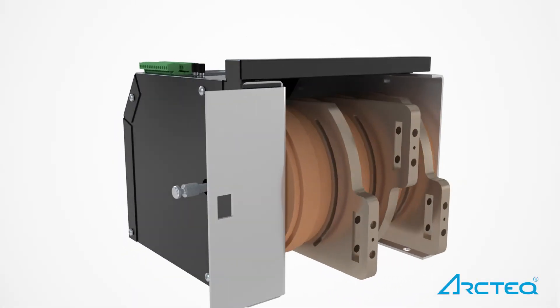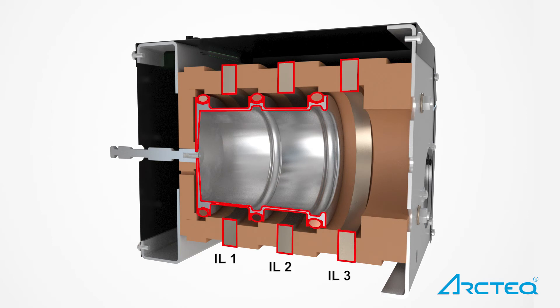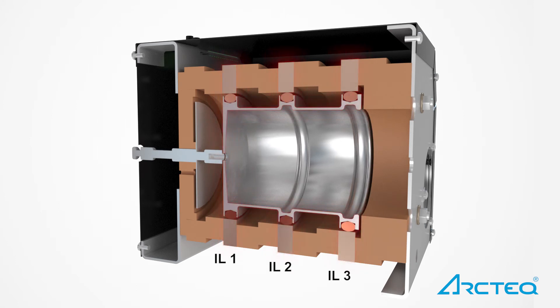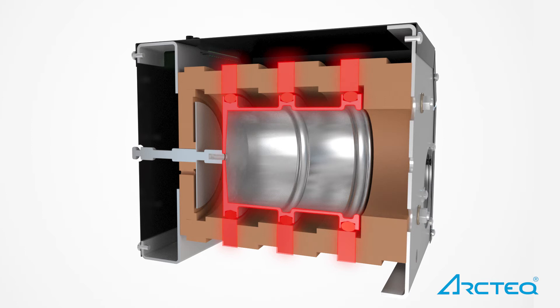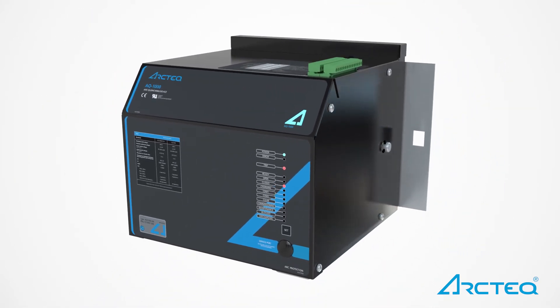The AQ1000 operation is based on patented and dependable Thomson coil technology. The bulletproof mechanism operating time is as little as 2 ms. The use of Thomson coil technology makes the AQ1000 fully reusable and testable. The system can be conveniently reset after factory or site testing.